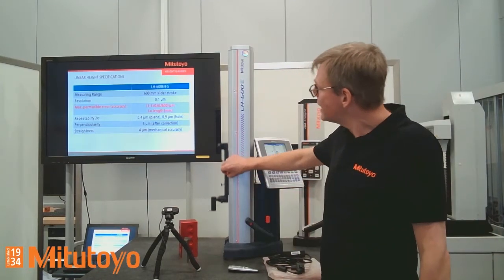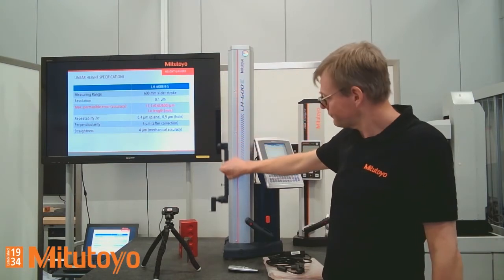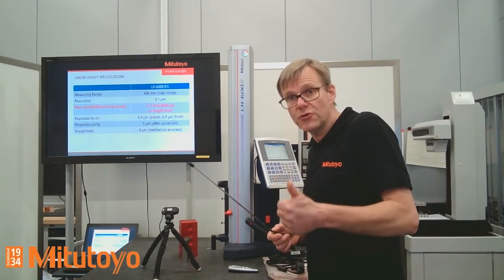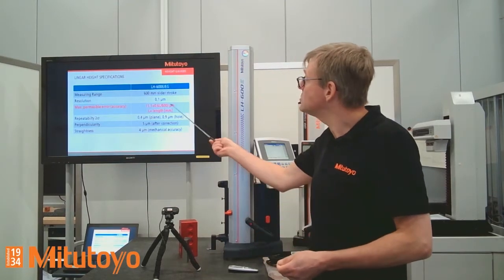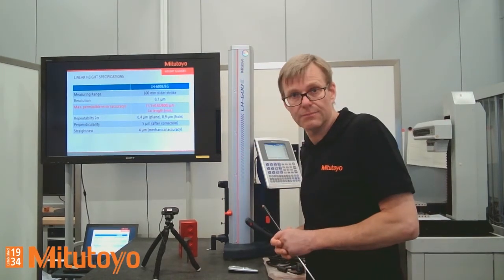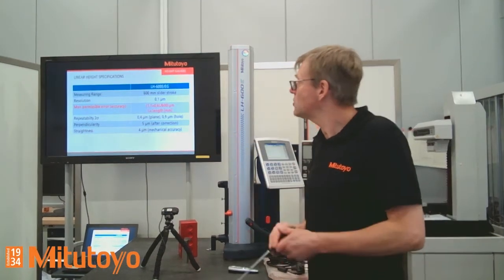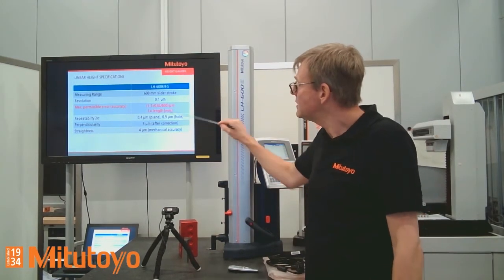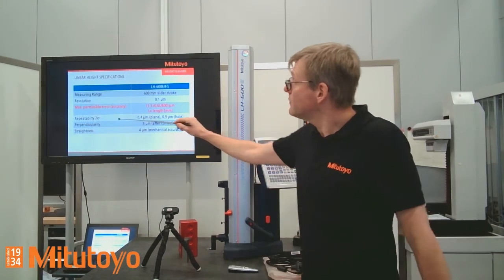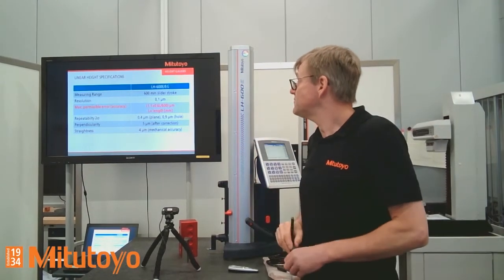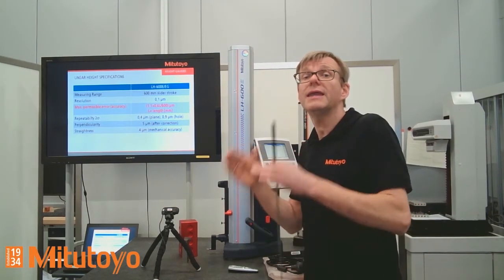So what is the specification of the Linear Height? This is on my next slide. First of all, we have a slider stroke of 600 millimeter. I told you this is a high accuracy measurement instrument. The digital step of this instrument is 0.1 micron, and the length accuracy is this one here, which is really extraordinary on the market. Furthermore, we have a specification of the repeatability on a plane, on a surface, and a repeatability inside a hole. We have a specification for perpendicularity, after compensation, after correction. And we have a straightness specification of 4 micrometer. This is a mechanical straightness.